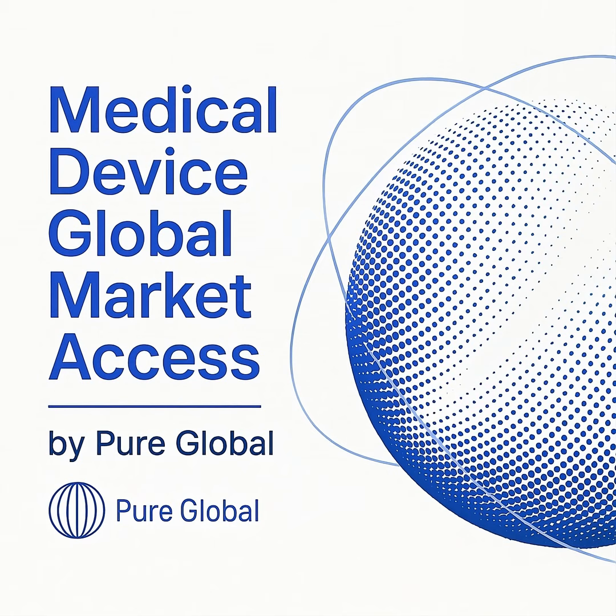The FDA has outlined specific expectations for descriptive information and testing to ensure the safety and effectiveness of these critical devices. Your 510(k) submission should now include a highly detailed device description with engineering drawings, a list of all components, and a comprehensive table of all materials used, especially those in the blood contact path. This sets the stage for the performance testing section, which is broken down into several key areas.